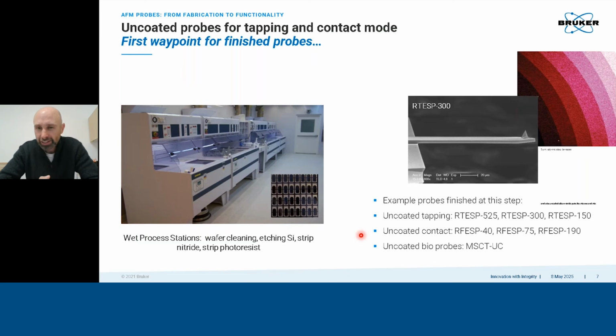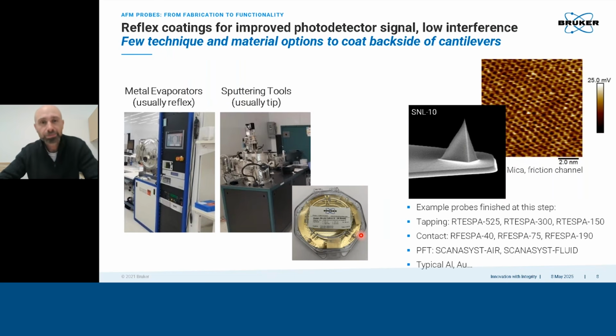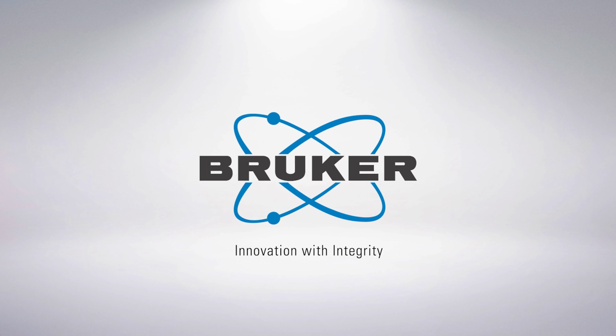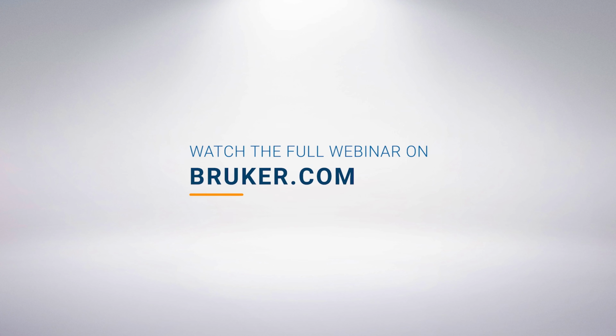And from the silicon nitride range, an example might be an MSCT-UC. The UC is uncoated. So that's an uncoated silicon nitride probe. So these probes can all be used, but, and it's a big but, I would say, 99% of the time, you want to be using a reflex or a detector side coated probe that has aluminum and gold on it. There are some applications where you might want an uncoated probe, or it might be because you want to deposit your own films on top. But again, 99% of people should be getting probes with backside coatings on, which takes me to my next step. So we have the raw probe, an uncoated silicon or silicon nitride, or combination thereof. And almost immediately we want to put a reflex coating on it.